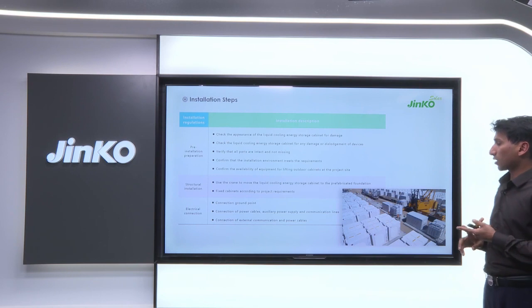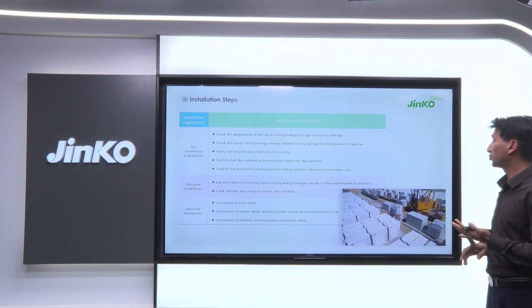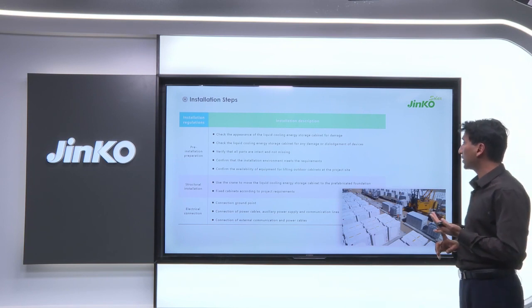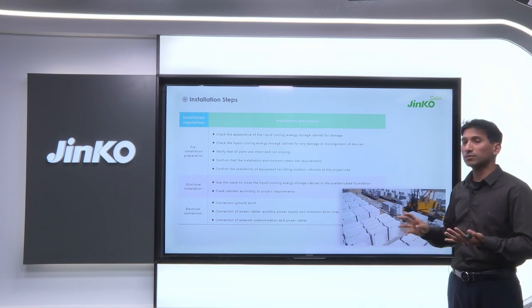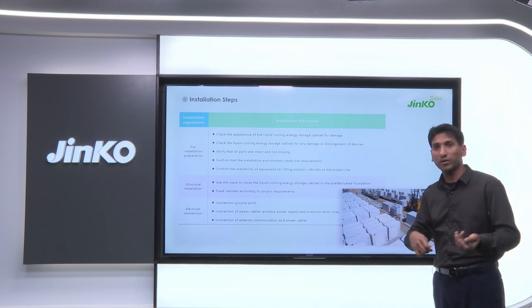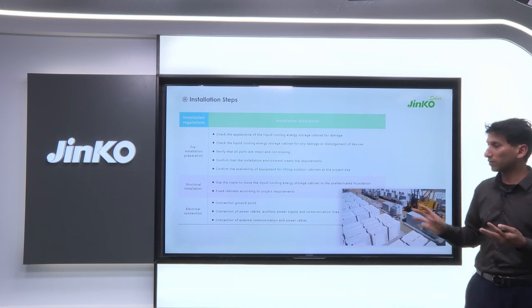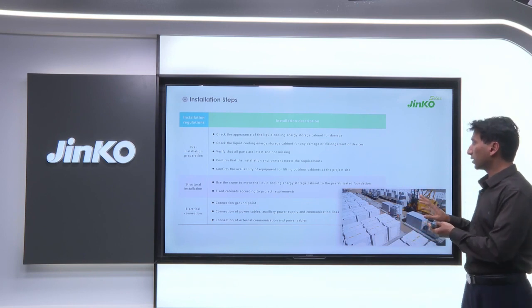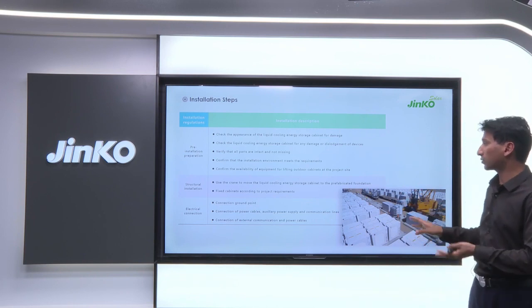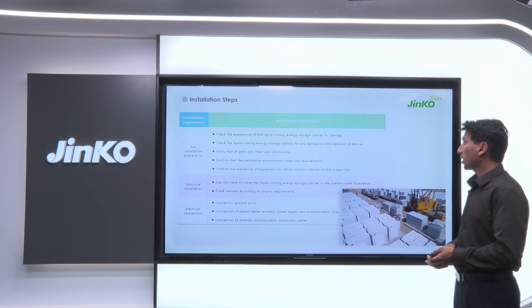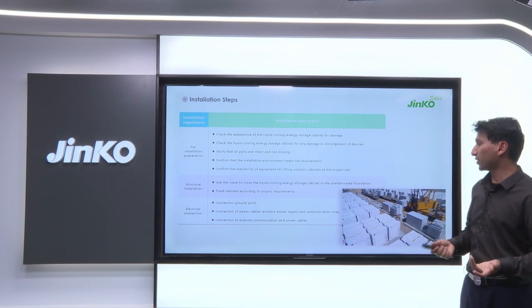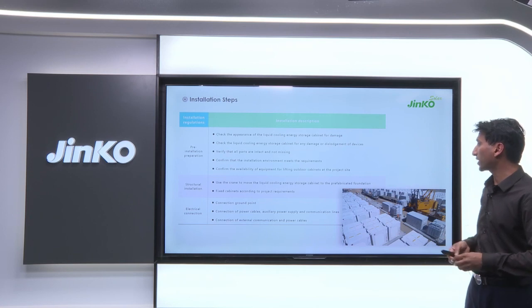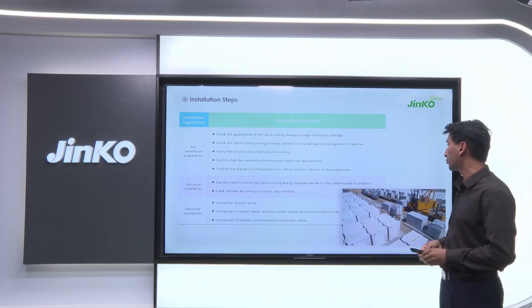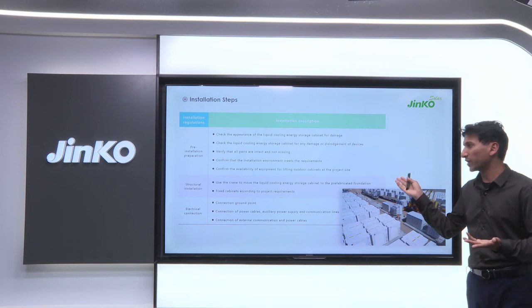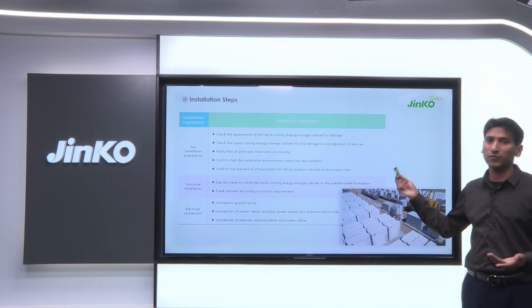In pre-installation, you check the appearance of the cabinet, check there is no damage to the devices inside, and that all devices are intact, since movement during shipping or trucking could dislodge them. Verify that all parts are intact and none are missing. Confirm that the installation environment meets requirements, and confirm the availability of equipment for lifting outdoor cabinets at the project site - these are all very common requirements you have to be careful about.